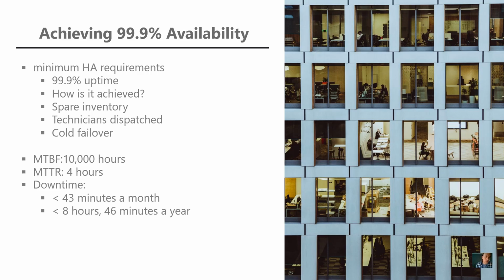One example: let's say the mean time between failures, MTBF, is 10,000 hours, and the time to repair is 4 hours. That gives you 99.9%, or 3 nines, which works out to 43 minutes a month of downtime, or 8 hours and 46 minutes a year.